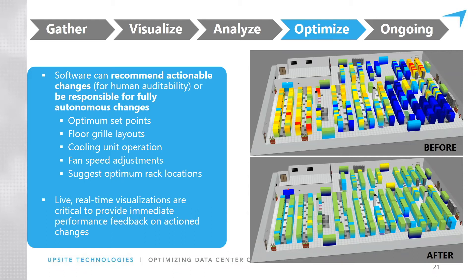It engages site personnel in the process of optimizing temperature set points, adjusting floor grilles, changing cooling unit fan speeds, and even suggesting recommendations for rack placement — analyzing and identifying where there is redundant cooling capacity in the room and where a new deployment can be supported. This is all done in real time and updated every few minutes; hundreds of thousands of data points can be collected per day and analyzed by these systems.